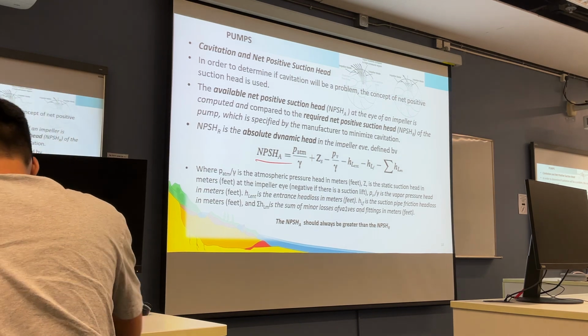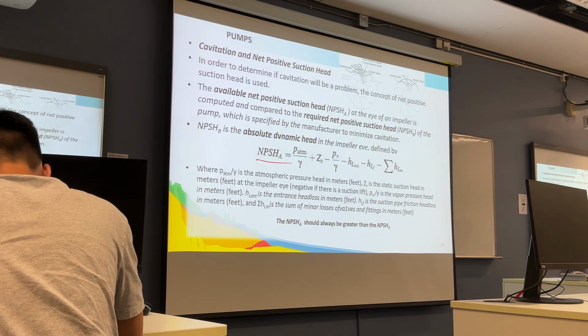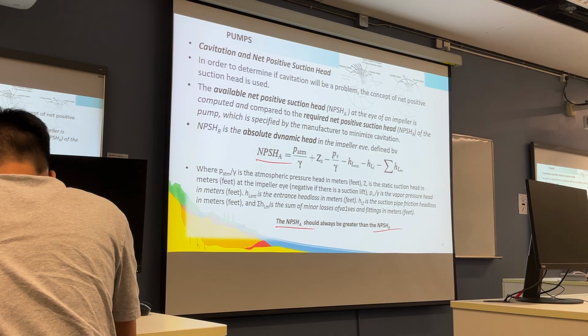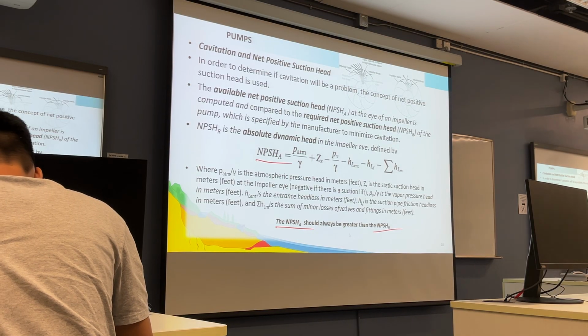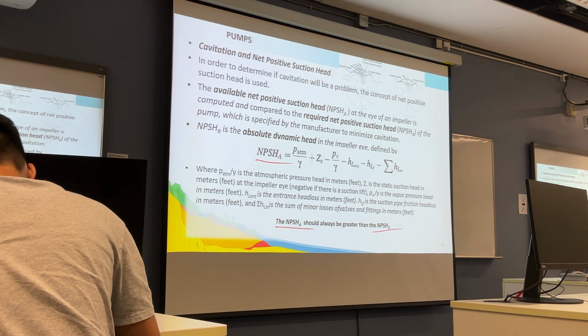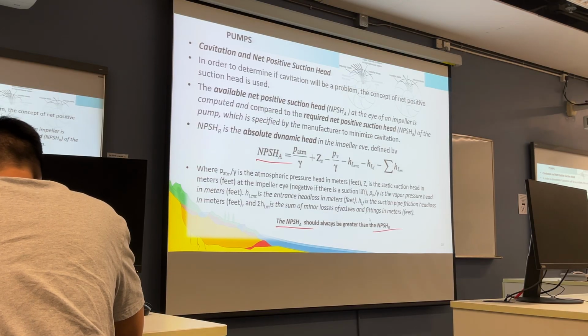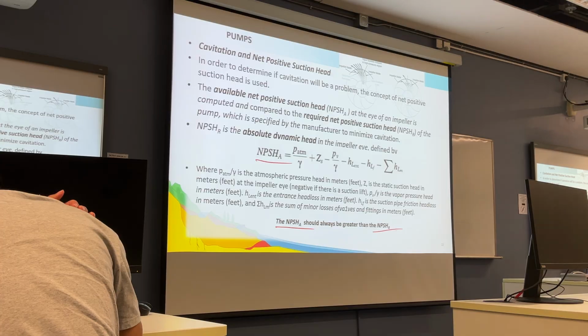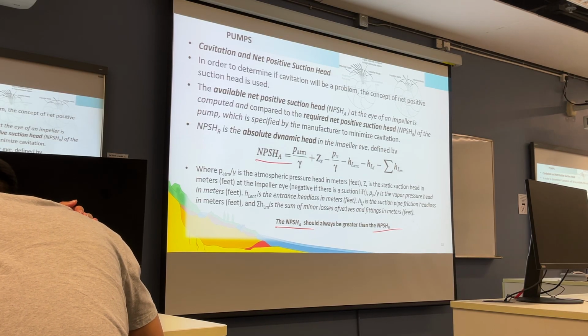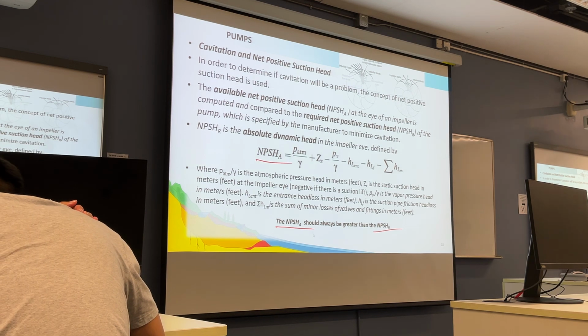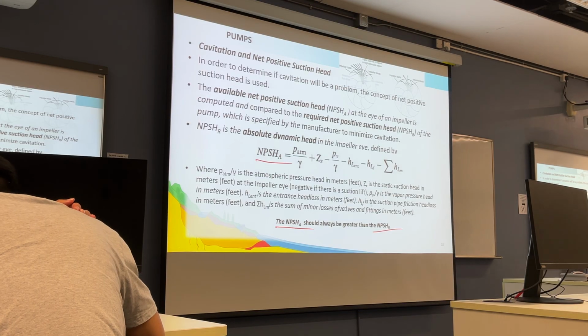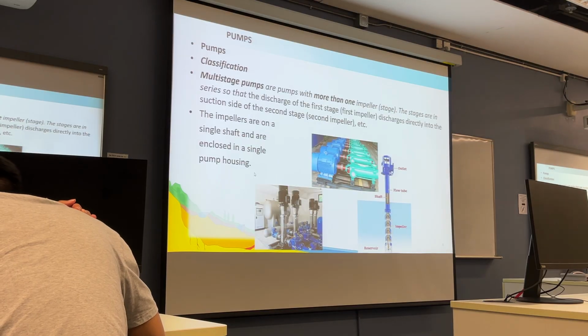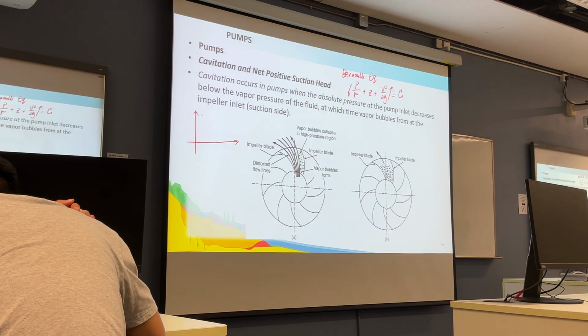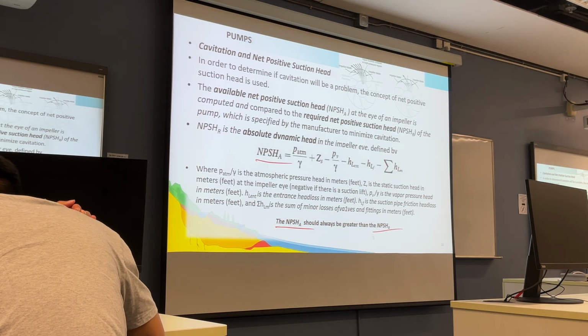So you will compare the NPSHA with the NPSHR, the actual or the available, and compare with the required suction head. Now this is usually provided by the spec or the catalog, from the pump manual. So that's what you will need to consider to calculate. This NPSHA is from your setup. You may need to have the NPSHA larger than this one, to ensure that the pump will have less chance of cavitation.